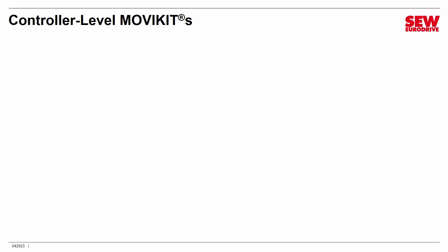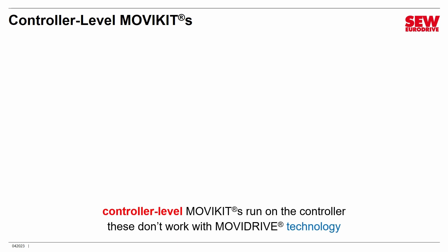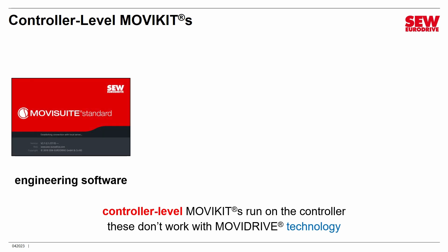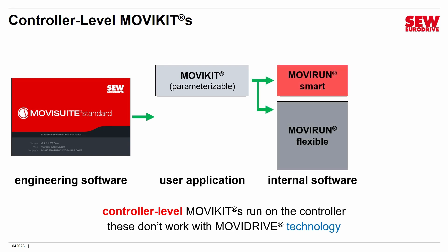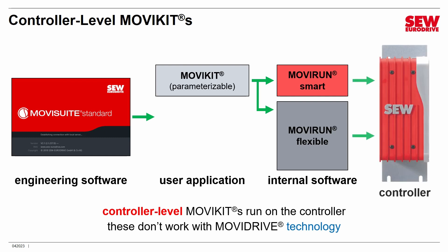Controller level MOVIKITs run on the controller — they can't be used with MOVIDRIVE technology since it has no controller. They run on the controller typically found in a MOVIDRIVE system or MOVIDRIVE modular installation, and you set them up using MOVISUITE. Parameterizable MOVIKITs are the simplest: set a few parameters and that becomes your user application. It then runs on either MOVIRUN smart or MOVIRUN flexible software in the controller, which manages the VFDs and access modules over the EtherCAT SBUS Plus network.